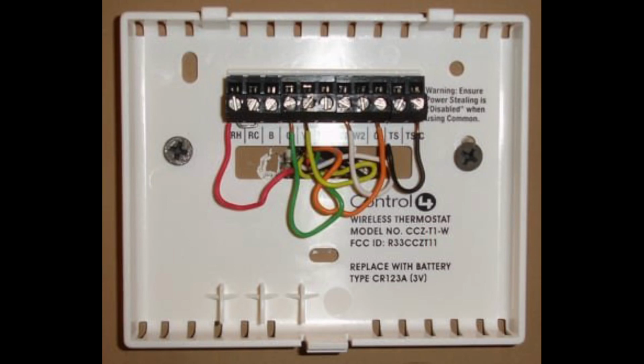G, the green one, remember I told you it's fan. Well, green goes to fan. Y is cool, and that is yellow. So if you kind of see how it's going, R for red, G for green wire, yellow for yellow, white for W2 for heat. Orange is for a reversing valve. This is a heat pump thermostat, and we will get into heat pumps in another video in addition. Black will be your emergency heat connection, and you can see that it's connected all the way over.